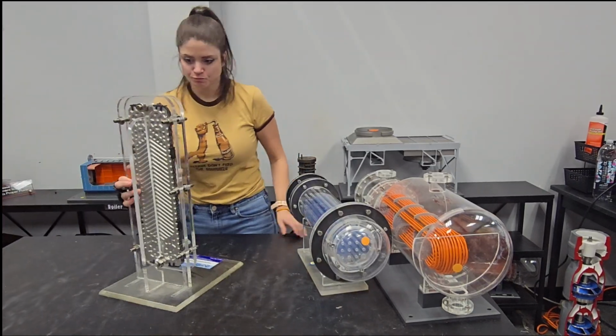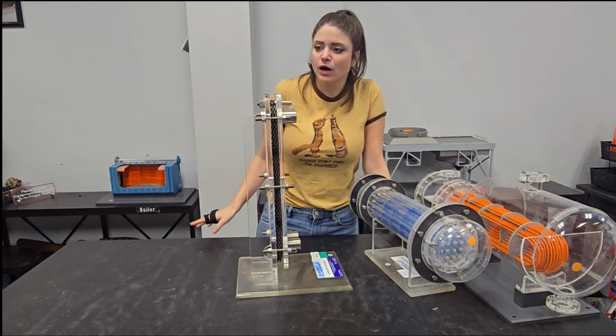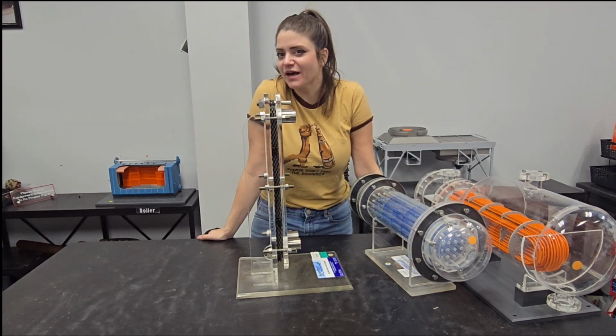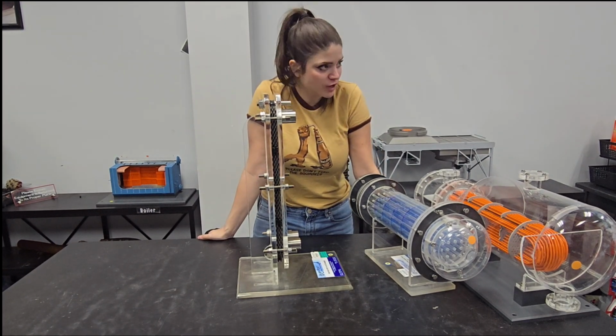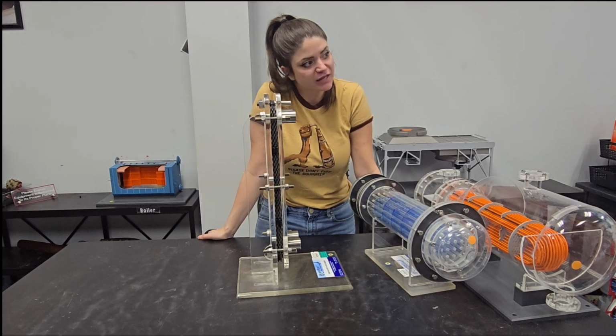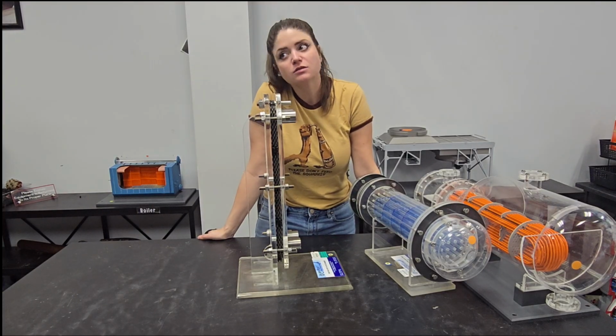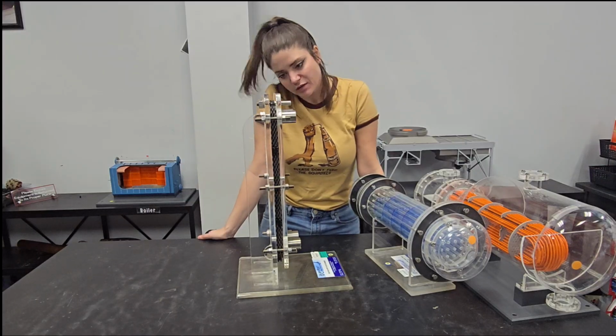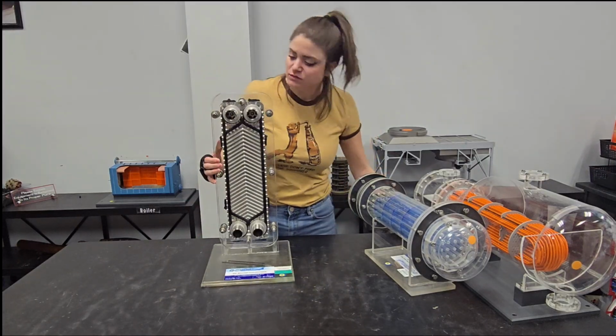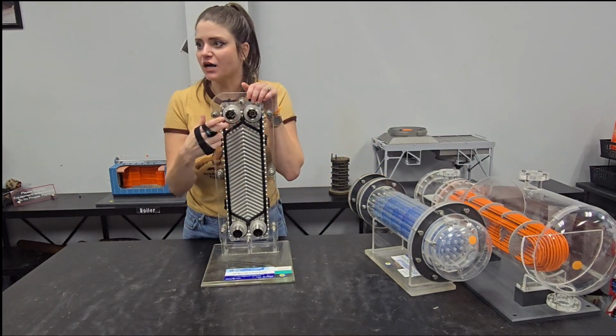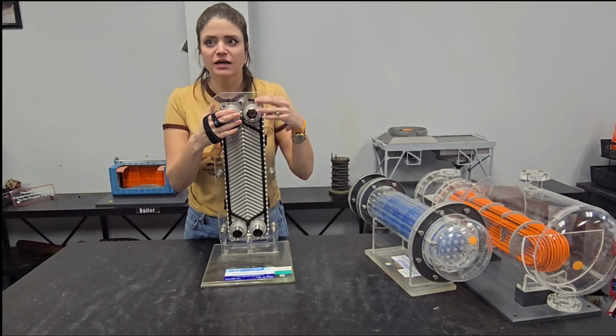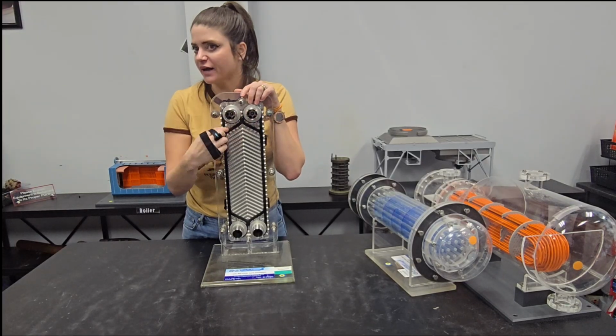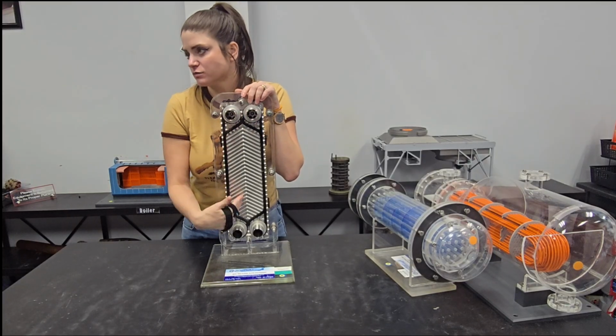Plate frame. How does it work? Pretty solid. Between each set, you're going to have a hot flow going through a set of plates, right? And then the next set of plates, or the opposite side of that plate, cold flow. And there will be gaskets that allow the hot side and cold side flow to come down from each plate, either there or not there, to allow the flow.